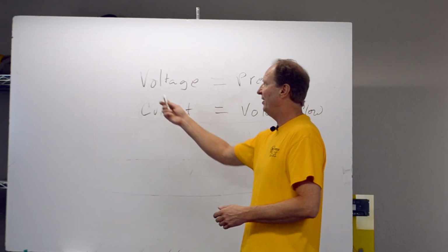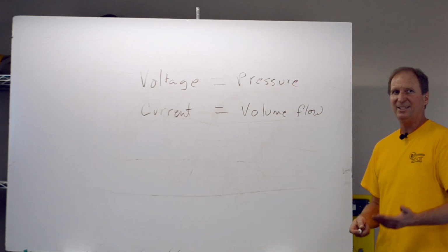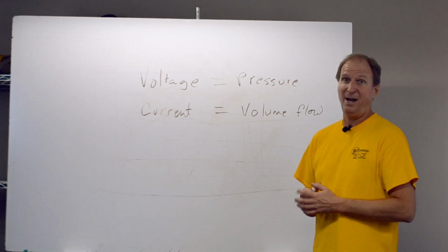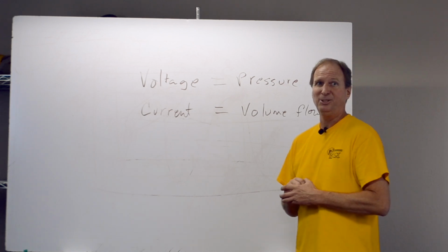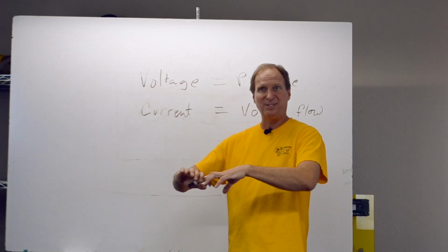That's because you don't have enough voltage to push the amount of current you're trying to get to the motor, and it slows down. In that case, you should feel those cables because they get smoking hot. They get near the limit of the insulation. And sometimes they exceed the limit of the insulation. You'll see that the cable starts getting soft and melting.